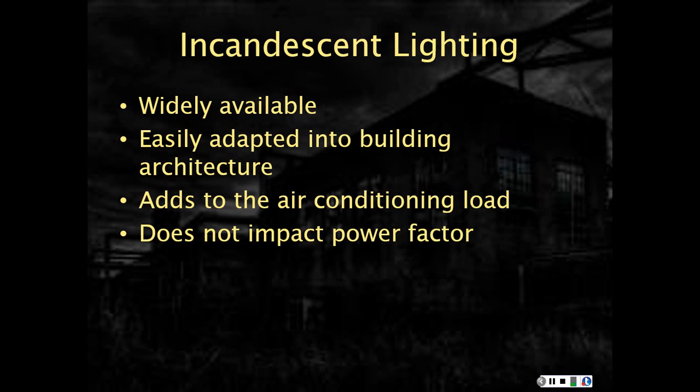They do add to the air conditioning load, which is another negative, but they also subtract from the heating load. They do not impact power factor because they don't have a ballast. And one other thing that's not on here that should be on here is they're easily modified to get a point source light. In other words, I can focus a light like in a spotlight or a floodlight, which is called point source lighting.